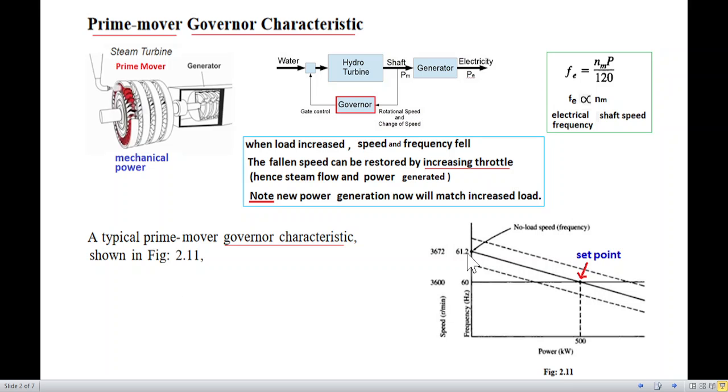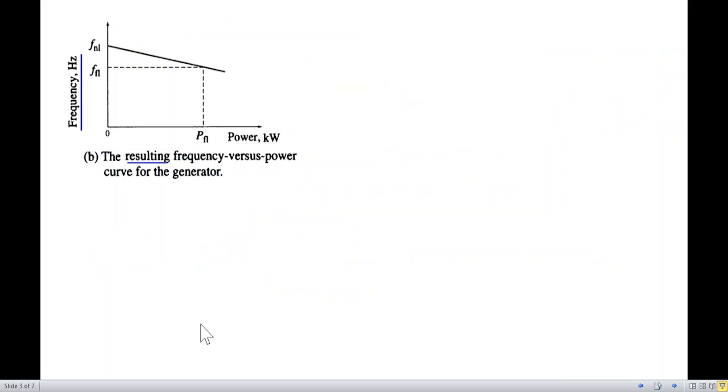We use this type of graph, which is known as the prime mover governor characteristics. This is also called slope. On one side is the power, and the other side is frequency, and also the speed. It is also called droop characteristics, and droop means inclined downwards.